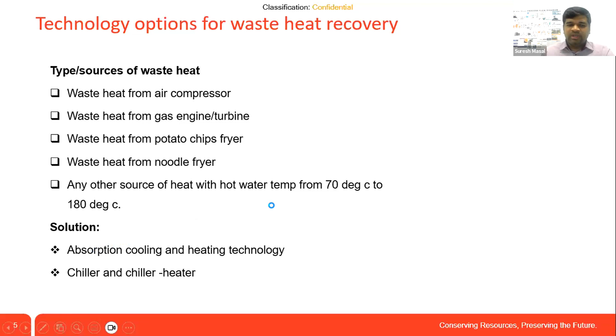So these are the types of heat normally available in any industry: waste heat from air compressors, waste heat from gas turbines or gas engines, waste heat from potato chips fryers, waste heat from noodle fryers, or any other heat source with hot water temperature ranging from 70 to 180 degrees, which can be used to generate cooling or heating. For this, the technology available is called absorption cooling and heating technology.